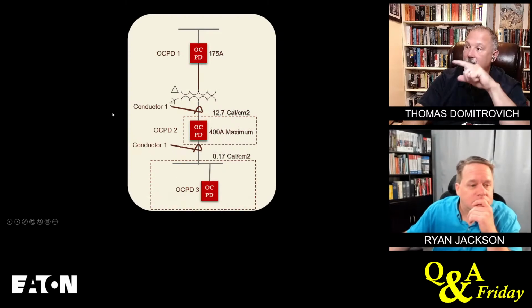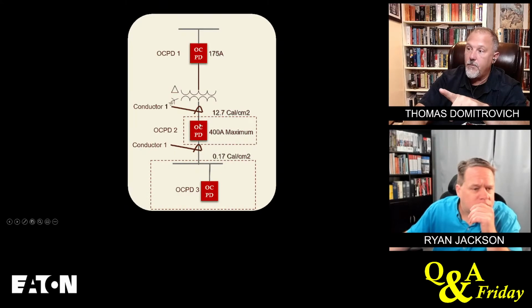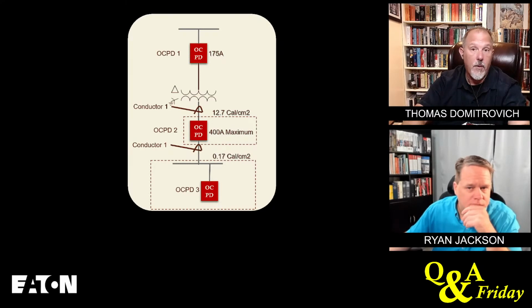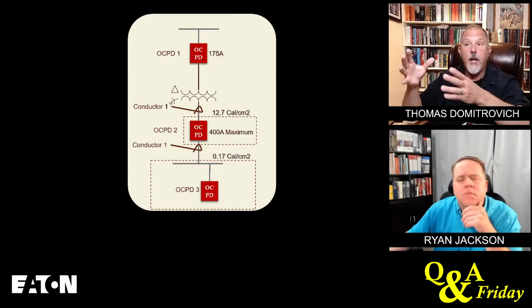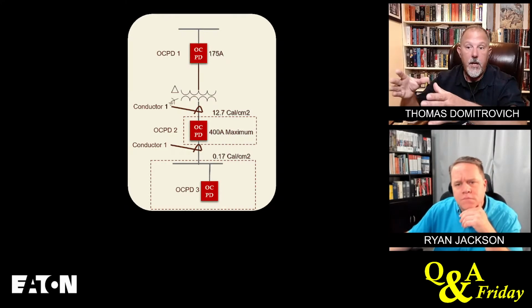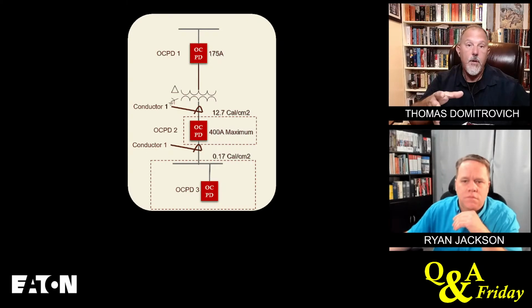You're right. Now, if I break this overcurrent protective device off and take it out of that panel board, I could put it in my transformer, right? My argument to this gentleman was, why don't you just put a disconnect right in front of that piece of equipment? We do that in our Beaver plant where we make circuit breakers. We put a circuit breaker in a box, and we put the arc reduction maintenance switch on it, supplying power to all of our control panels and stuff like that.